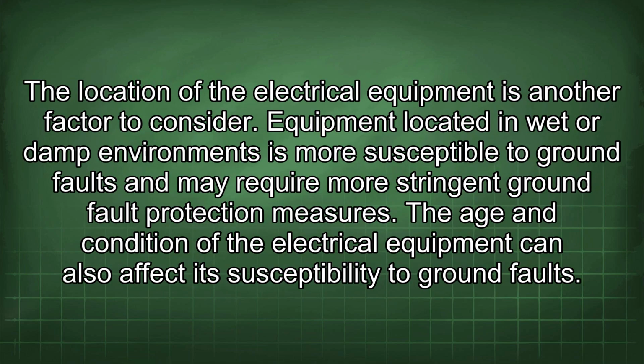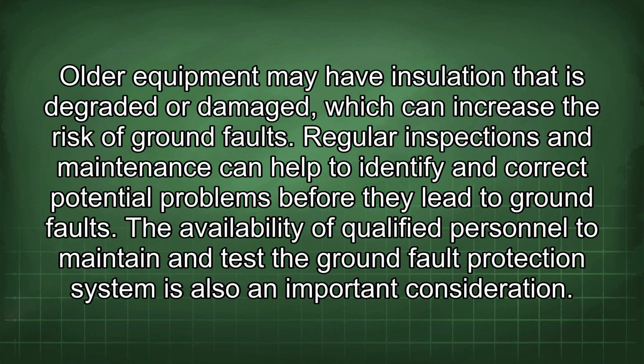The location of the electrical equipment is another factor to consider. Equipment located in wet or damp environments is more susceptible to ground faults and may require more stringent ground fault protection measures. The age and condition of the electrical equipment can also affect its susceptibility to ground faults. Older equipment may have insulation that is degraded or damaged, which can increase the risk of ground faults. Regular inspections and maintenance can help to identify and correct potential problems before they lead to ground faults.